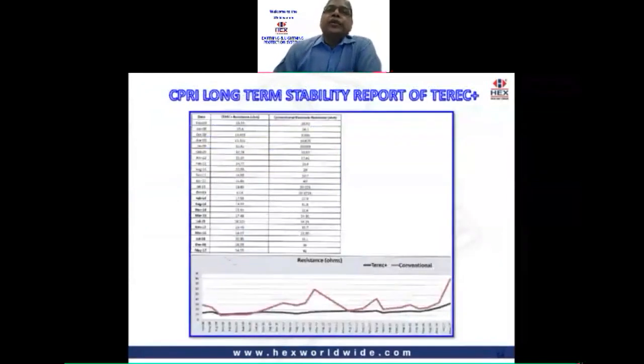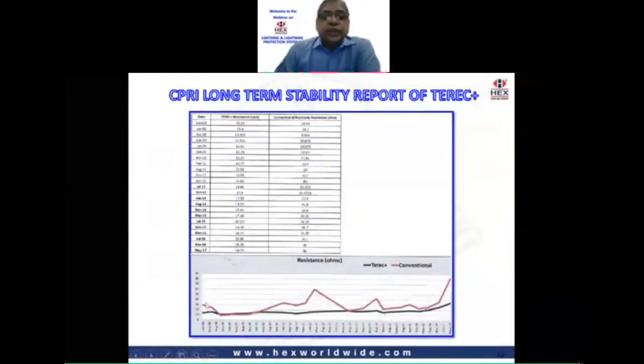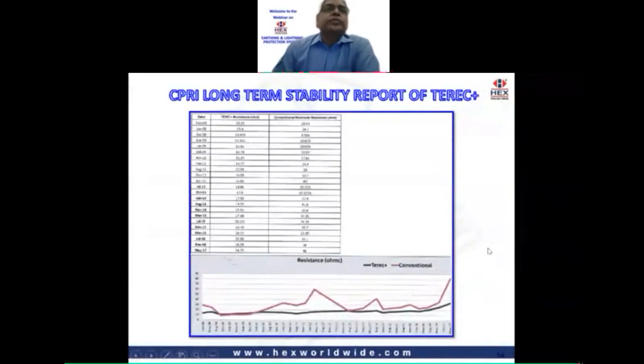We also have done a long-term test study along with CPRI of Bangalore in two earth pits. The one was filled with Terec+ and the other with a conventional salt and charcoal in 2008. The resistance values till May 2017 are given in this table. This black line here is of Terec+, which shows a very, very stable performance. And the red line is of the conventional salt and charcoal earth pit, which shows a very, very erratic behavior in its resistance values.